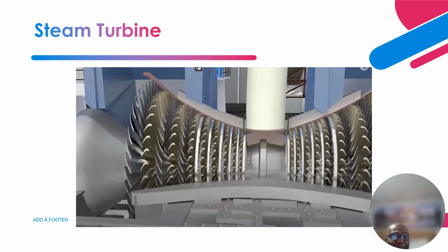So this is a much closer picture of how the turbine blades look. As you can see, it's in the form of an aerofoil, just like an airplane aerofoil. So it has an aerodynamic shape. The goal is to create that aerodynamic shape and also to reduce resonances and minimize sound. And there's also something they call solid particle erosion. As steam impinges on these surfaces, the steam itself has sediments that are part of it, and that sediment could erode the surfaces of these turbine blades. So the blades are shaped in such a way that it minimizes that solid particle erosion.